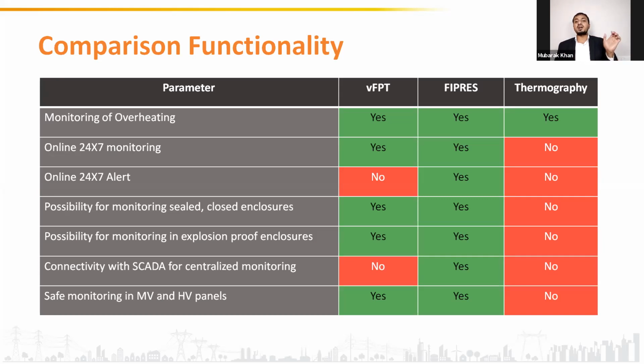Are we getting a 24/7 alert? In VFPT, no. In FIPRES, yes. Thermography, no. Now, the possibility of monitoring sealed enclosures, like high voltage panels and explosion proof panels. With thermography, we cannot monitor the locked and explosion proof high voltage panels, but with VFPT and FIPRES, we can monitor. Similarly, for explosion proof enclosures, we cannot monitor with thermography, but we can with VFPT and FIPRES.